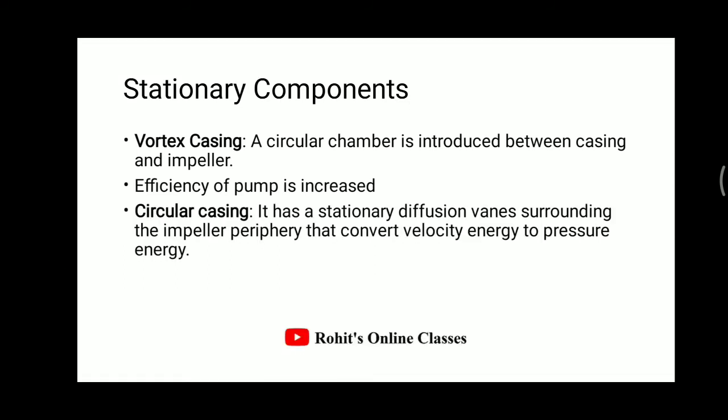The third type is circular casing. It is a stationary diffusion ring surrounding the impeller periphery that converts velocity energy into pressure energy. It is generally used for lower heads. The velocity energy — that is, kinetic energy of the fluid — is converted into pressure energy. It is also known as diffuser ring casing.